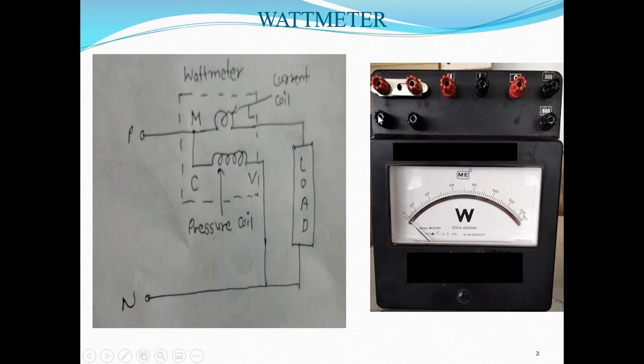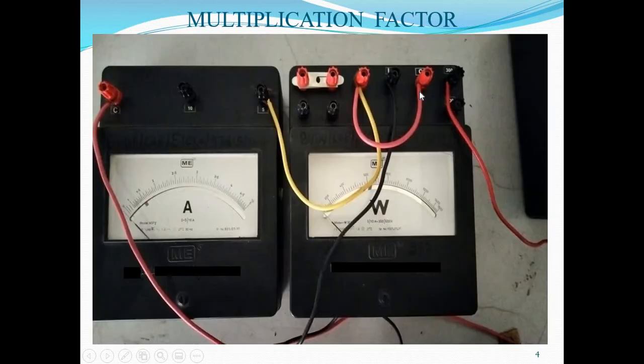If the plates are connected vertically, that shows the watt meter is used for high range purpose. Right now it is used for low range. The multiplication factor is also given on this watt meter. If the voltage range is 300 and current range is low — that is 5 ampere — then the multiplier is 1. Using the theoretical formula: 300 into 5 into 1, divided by 1500, equals 1. Similarly, for voltage range 300 and current range 10: 300 into 10 into 1, divided by 1500, equals 2.